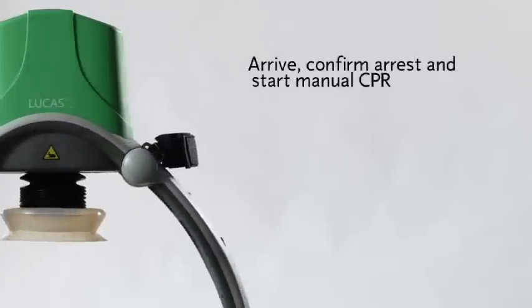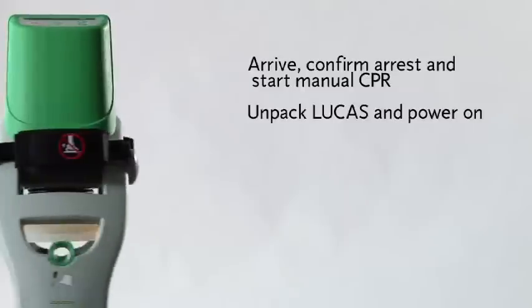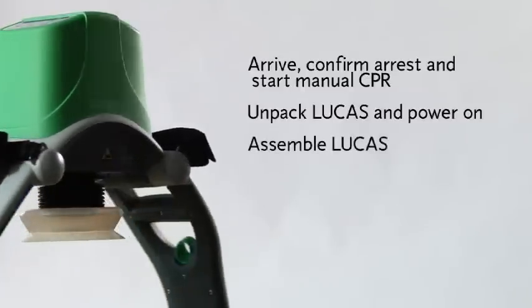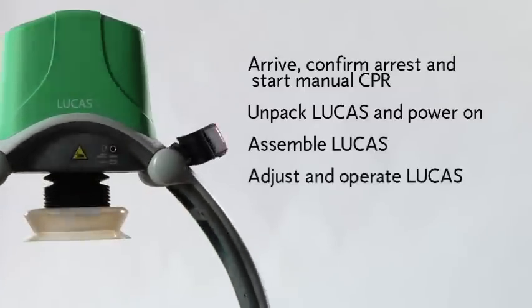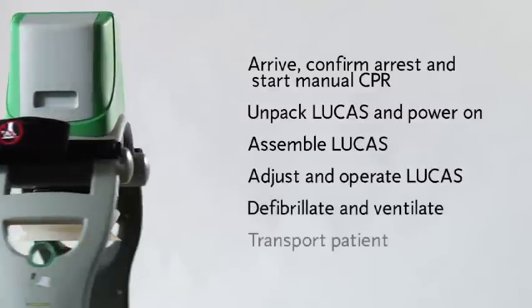Now let's step through the basics of how to use it. The basic steps for using LUCAS are: arrive, confirm cardiac arrest, and start manual CPR; unpack LUCAS and power it on; assemble LUCAS on the patient; adjust and operate LUCAS; defibrillate and ventilate; and transport the patient.